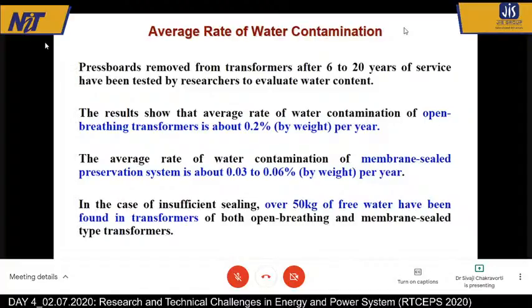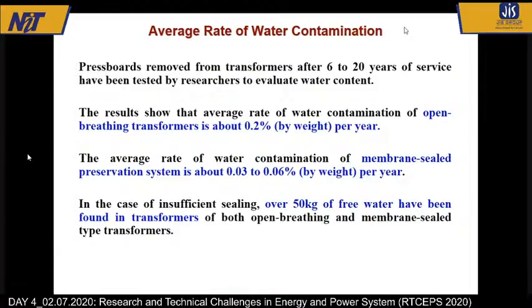Nowadays, all the high voltage, 132 kV or 400 kV transformers, are membrane sealed, which means that the top of the conservator tank is not connected to atmospheric air. There is a membrane, so moisture cannot directly come in contact with the oil. And in that case, moisture ingress reduces significantly. It is around 0.06% by weight. It is very, very significantly lowered. But if the sealing I was talking about, the top cover sealing or oil drain valve sealing, is poor, then a lot of free water can go in, even with the membrane seal. Today we take special care about that sealing.